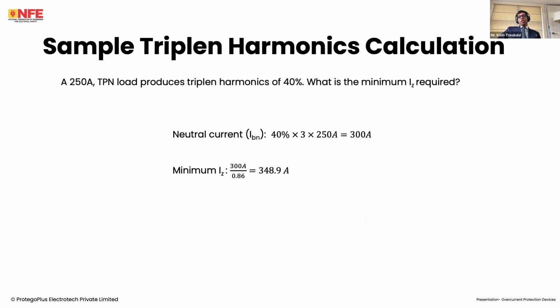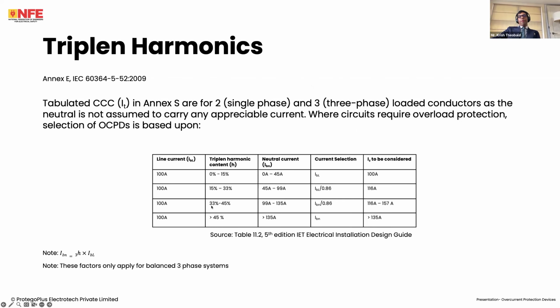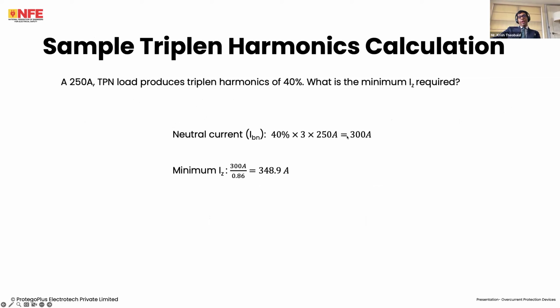Look at an example calculation. If we consider a 250 amp load with 40% total harmonic distortion due to triplen harmonics, 40% of 3 times 250 is 300 amps flowing in the neutral. Because we are between the 33 to 45% threshold, selection is based on the neutral conductor current. So we need to know the current in the neutral: 300 amps. 300 amps divided by 0.86 is 348.9 amps.